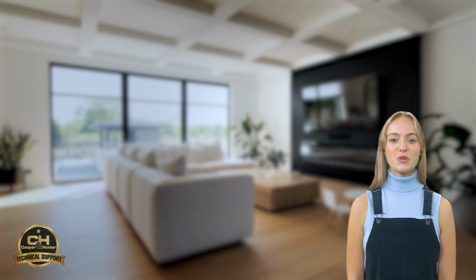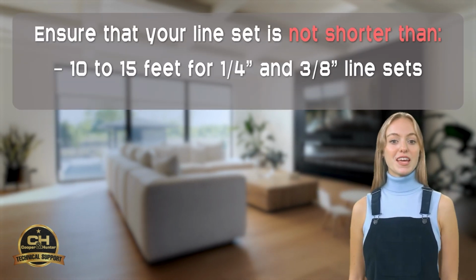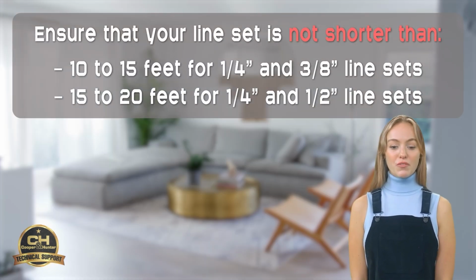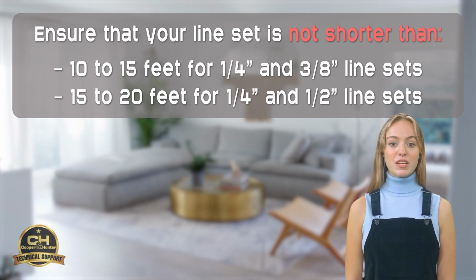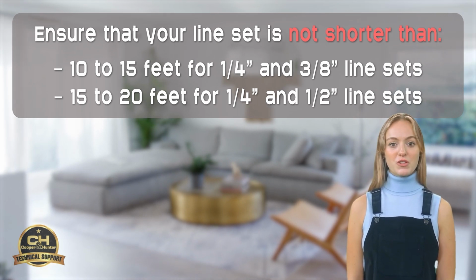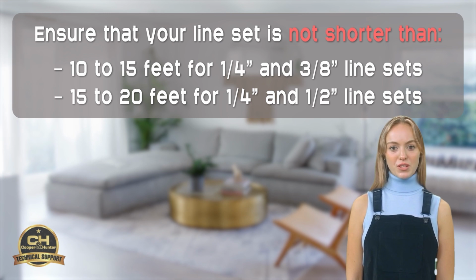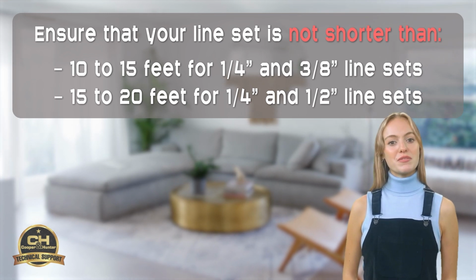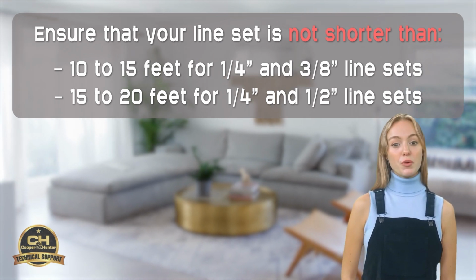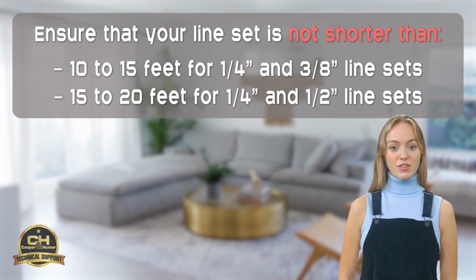However, please ensure that your line set is not shorter than 10 to 15 feet for 1/4 of an inch and 3/8 of an inch line sets, or 15 to 20 feet for 1/4 of an inch and 1/2 of an inch line sets. These are the recommended minimum lengths for optimal performance and efficiency of the equipment.